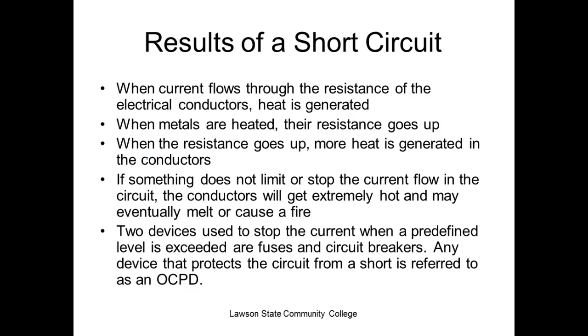They'll eventually go out. So a circuit breaker shouldn't get hot, and it should never drop a voltage. If you've got a circuit breaker that's popping all the time, it might not be because you're overloading the breaker. It might be the breaker's going bad. So when you reset it and you measure the voltage across it, between your neutral and your hot, between the output, it should measure almost 0 volts. If it measures 5-6 volts, you need to go ahead and do what? Replace it. Overcurrent protection devices should drop almost no voltage.